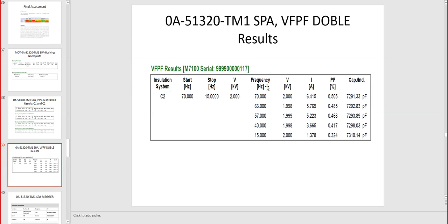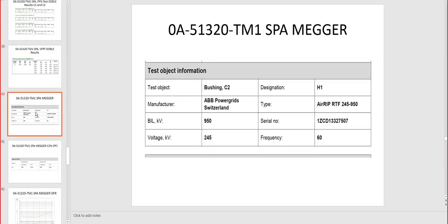The results here are for different frequencies, so the same test but now applied for the same bushing with 2 kilovolts, and frequency was increased from 15 hertz, then 40, 57, 63 and 70. And these are the results with the power factor, the current applied, and then the total current, and then the capacitance in picofarads. So that concludes here the bushing on C2, manufacturer ABB, and that's on the secondary. So now we have the 245 kV. Sorry, it's the same bushing on the H1, but it's 245 kilovolts from the tap that you can apply.